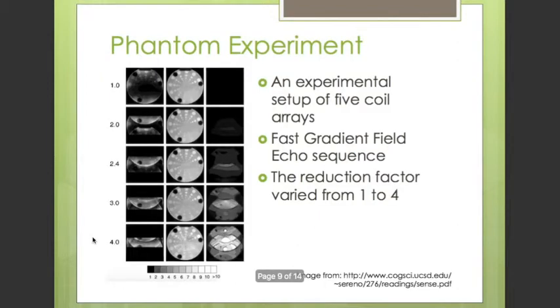Some phantom experiments have been conducted with different reduction factors. An experimental setup of five coil arrays was arranged and a fast gradient field echo sequence was used. The reduction factor varied from 1 to 4, with one indicating no reduction. The left column shows the conventional sum of squares, the middle shows the SENSE reconstruction, and the right column shows the noise. Although the images don't show a significant artifact with increasing reduction factor, they show an inhomogeneity in noise distribution, with higher noise intensity in the middle.